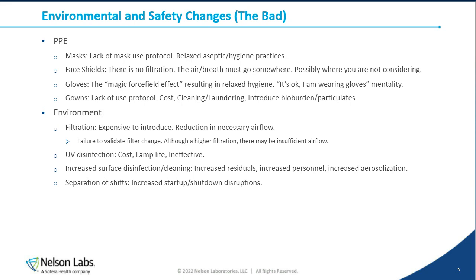On the environmental side, it would seem at first glance that if you're introducing filtration, the expectation is that you're going to have improved air quality. But without proper planning, proper engineering, and proper change control to go with it, that can actually lead to issues such as a reduction in the necessary airflow. So areas that should have been at positive pressure now have reduced airflow, and they're no longer at that positive pressure environment.